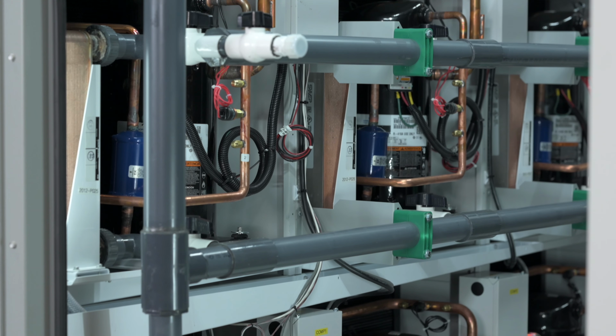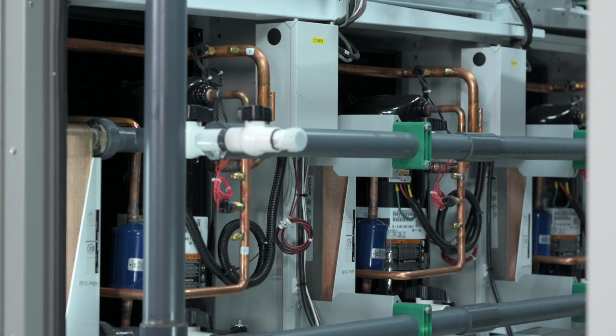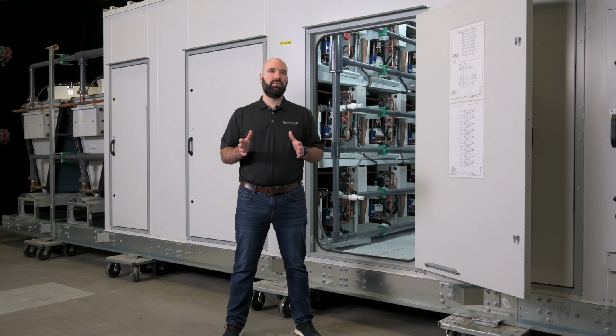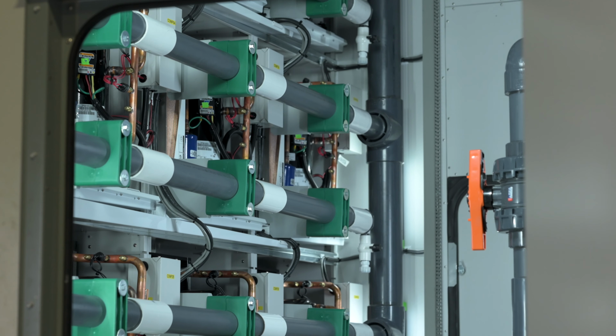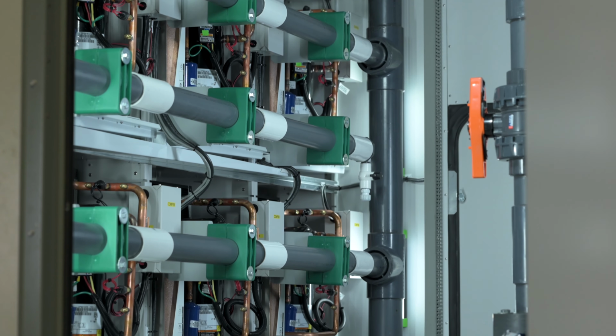In this other side now of that same section, you'll see behind me the 9 compressor pods that make up the 55-ton unit. Our compressor wall technology uses multiple small refrigeration pods, either 6.3 or 7.6 nominal tons, and uses them in multiples to create whatever nominal tonnage the facility needs. Again, this 55-ton unit using 9 of them. The product line itself goes all the way down to a 10-ton unit using only 2 pods to a 120-ton unit using 16 of them.